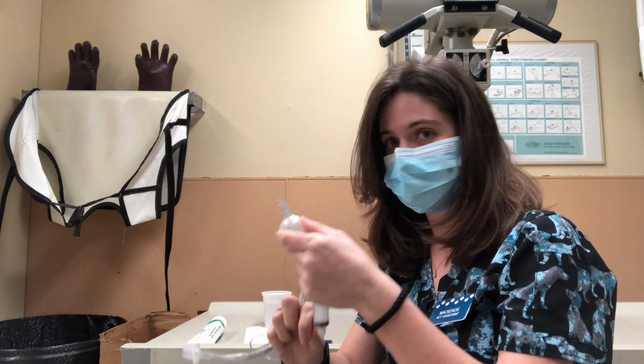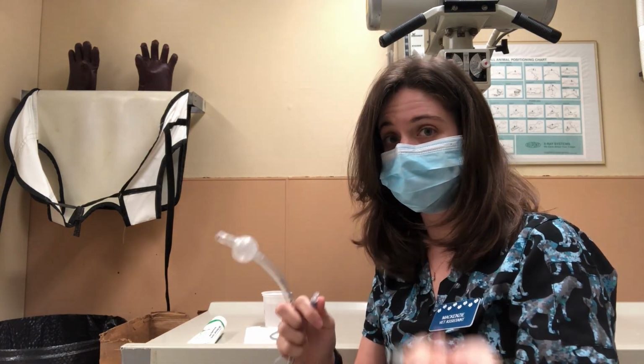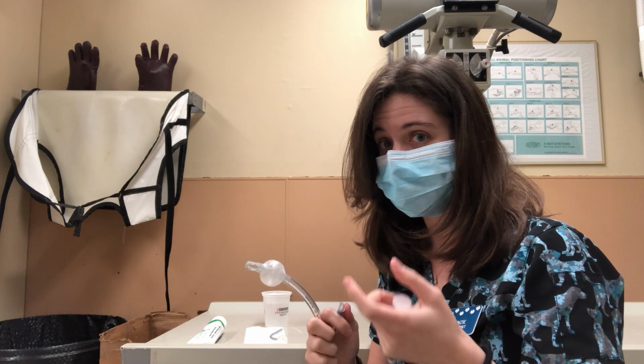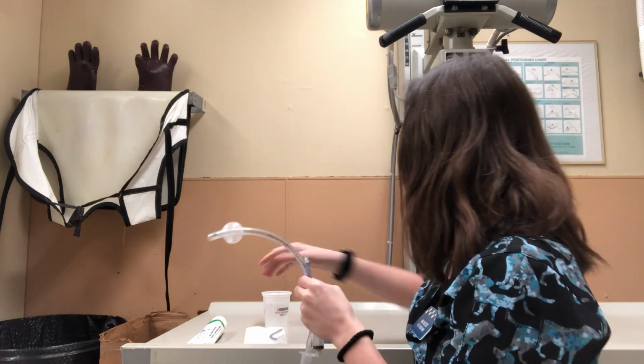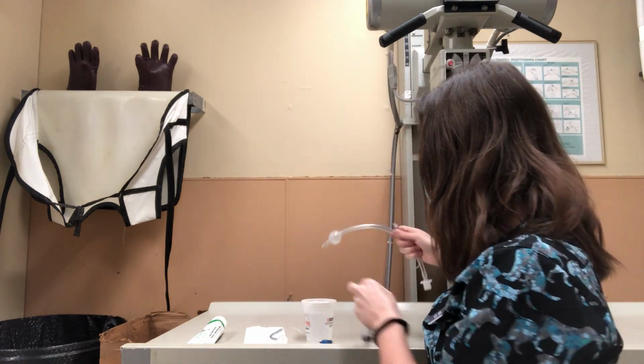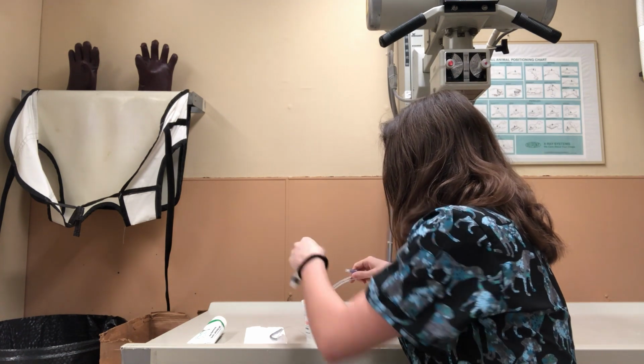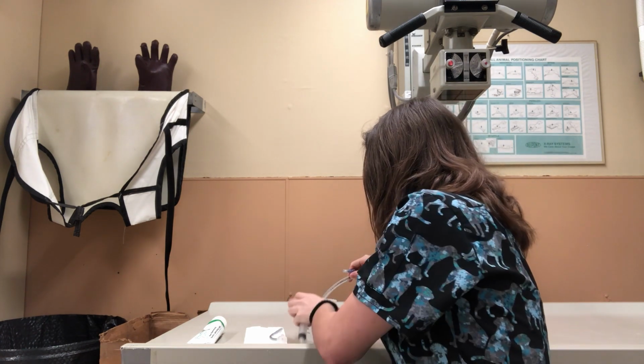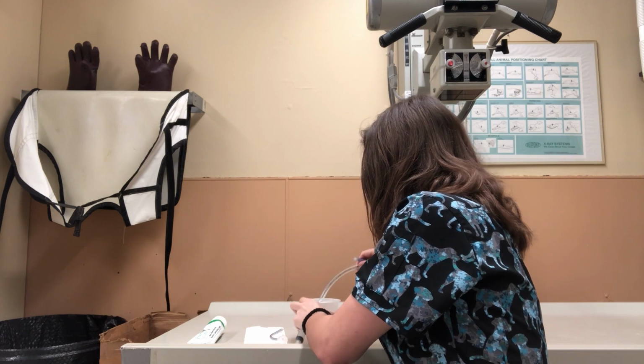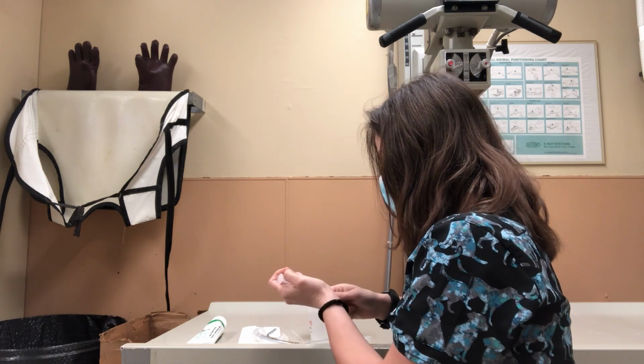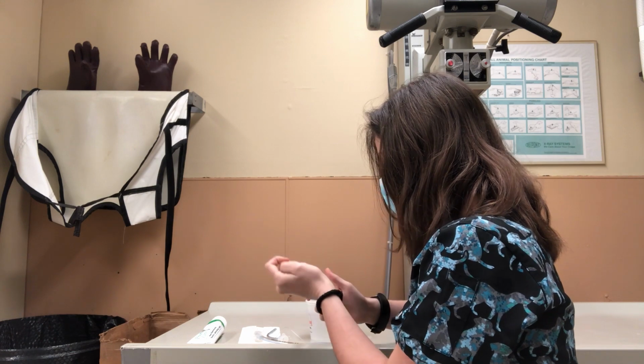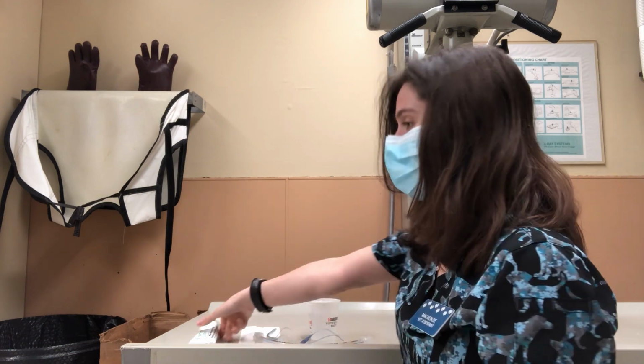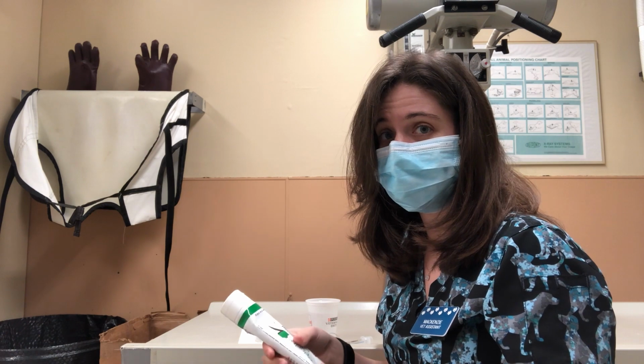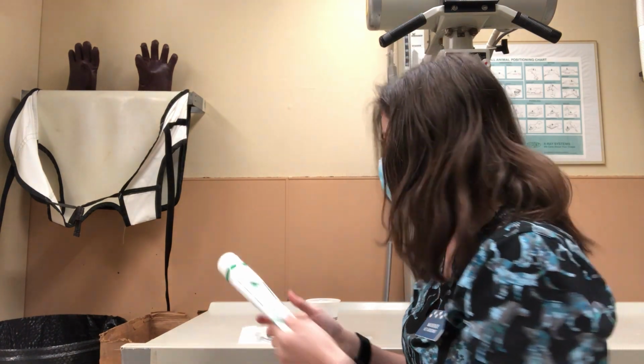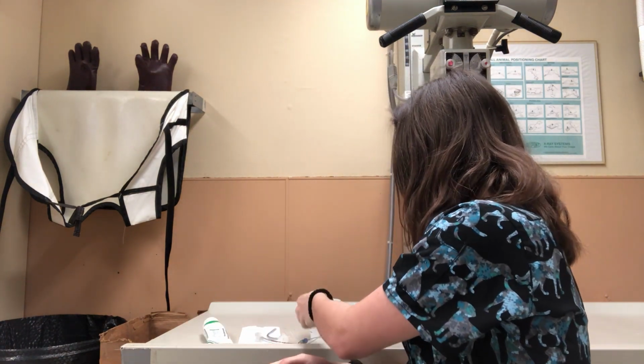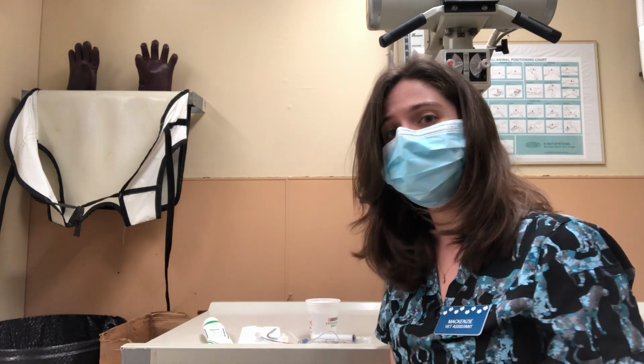And just looking at it, you can see that it's retaining its shape. To check to make sure that there's no little leaking anywhere going on, we want to submerge the cuff into a cup of water and see if we get any bubbles. The bubbles would indicate a leak. And I'm not seeing any bubbles here, so I would assume that this cuff is intact and not leaking at all. And then of course we want to use our lubricant to make it easier for the tube to go down. We would lube the cuff itself and the tip of the tube.